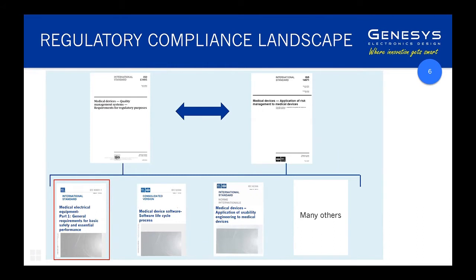60601-1 is the headline standard relating to basic safety and essential performance. It's important to note that it's not just electrical safety — it tends to get misquoted as such. It's actually the safety of electrical equipment. As you'll see through the presentation, there is a lot in this for industrial designers, mechanical engineers, and mechatronics engineers — in some products a greater role than for the electrical engineers.